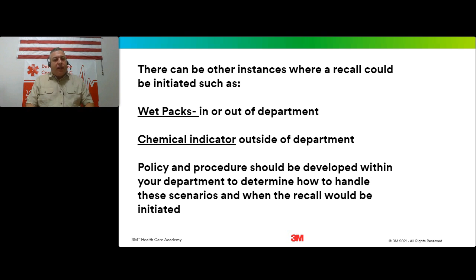We're not necessarily saying that's an immediate recall, but that is an area where you need to develop and determine your pathways. You need to decide what your process is if a single device goes upstairs and there is wetness inside. You can use the guidance documents, get your team together, and determine what you're going to do. Are you going to inspect? Are you going to reject the entire load at that point? Or are you going to do random sampling? It really is up to your department to use the guidelines and determine how your individual facility is going to handle that.